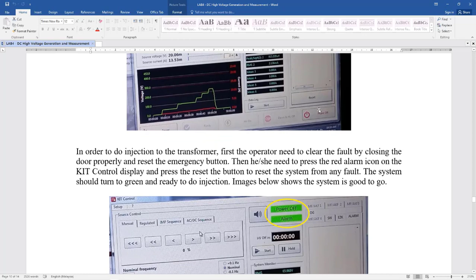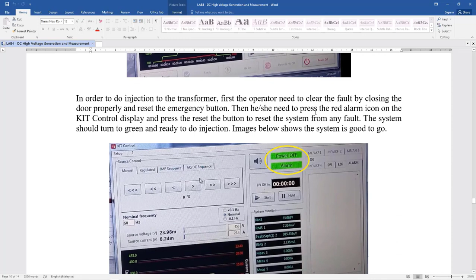The operator needs to reset the emergency button here and close the door properly. Then the operator needs to press the red alarm button here and press the reset button here, and the system should turn green and be ready to do injection. So this is the display when there is no alarm in the system. The system is good to go.